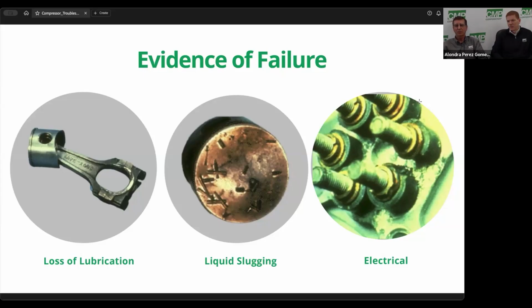And if you're changing a compressor out on a rack, and I'm sure, Trevor, you probably touched on this, it'll have a little plate in your discharge line that's got a bunch of little holes in it. And that's for vibration purposes also. You'll change the compressor and you'll be lazy and you won't want to scrape those gaskets off of that little thin plate. But you need to scrape them off there real good and change that gasket, put that plate back on there, because that's exactly what that plate does, vibration.